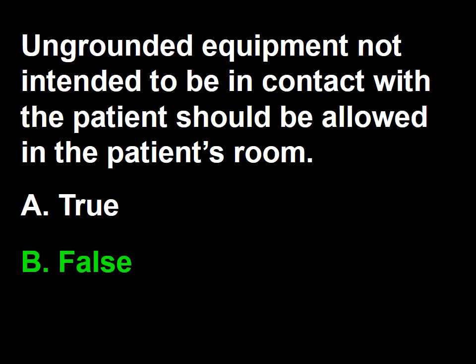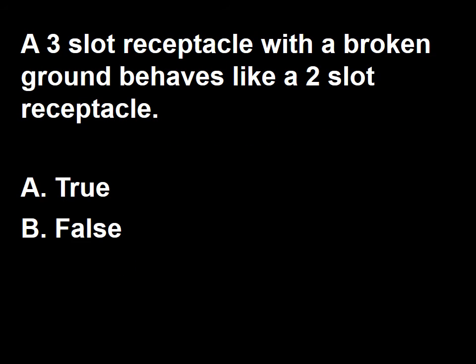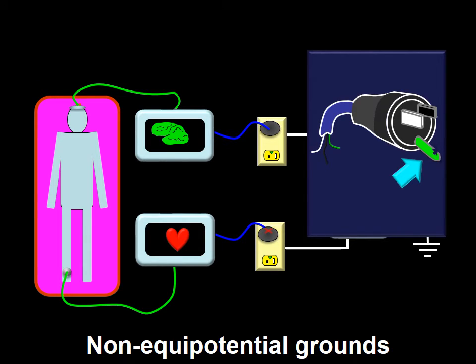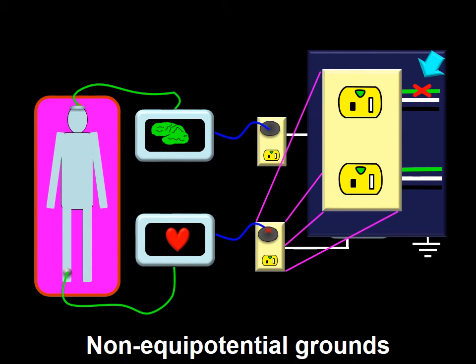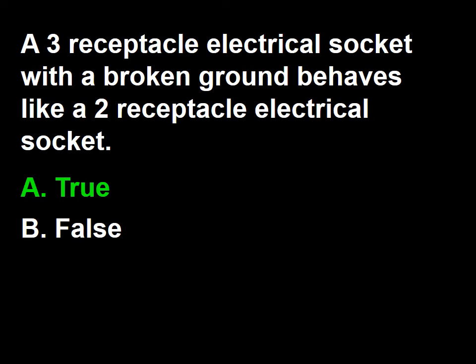The next question: a three-slot receptacle with a broken ground behaves like a two-slot receptacle — true or false? The broken ground pin provides more resistance than an unbroken one. So does a broken line between the electrical receptacle and the electrical box. In both of these cases, the broken ground will render the three-slot receptacle as an ungrounded two-slot receptacle. The answer to this question is A — true.